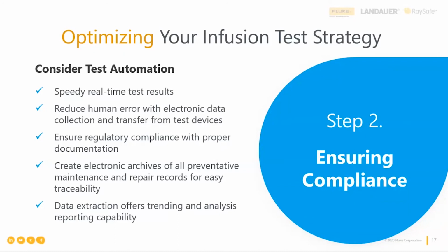It's going to allow us to collect all of our actions in that workflow. So we already highlighted the sections of the workflow: the visual and physical inspection of the device, the electrical safety measurements around the device, the preventive maintenance that may be done, and the performance tests. We can collect all of that and get just one test report at the end. And that's really important. It speeds everything up.